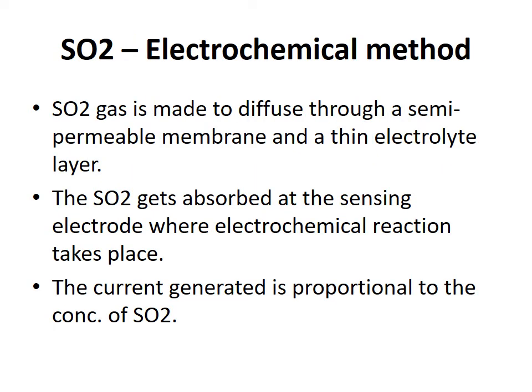The next method for SO₂ analysis in stack gases is the electrochemical method. The SO₂ gas is made to diffuse through a semi-permeable membrane and a thin electrolyte layer. The sulfur dioxide gets adsorbed at the sensing electrode where the electrochemical reaction takes place, and the current generated is proportional to the concentration of sulfur dioxide.